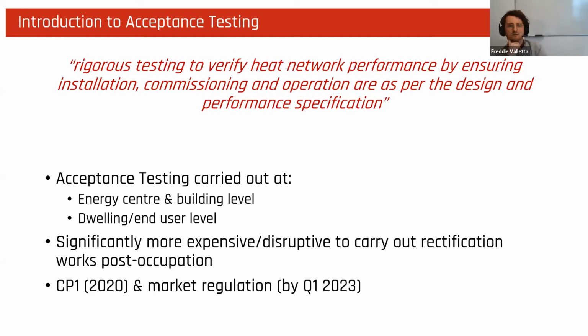Typically, this term has been focused on dwelling level tests. However, now it's being introduced as a catch-all term applying to performance tests carried out in the energy center and at a building level as well. This process was developed to ensure that all performance issues with individual units and the system as a cohesive unit are addressed, as it's significantly more expensive and disruptive to carry out rectification works post-occupation.